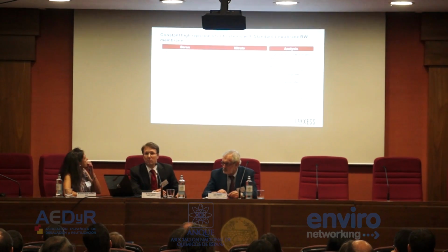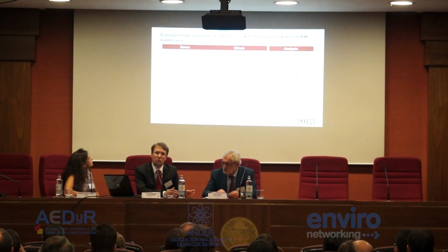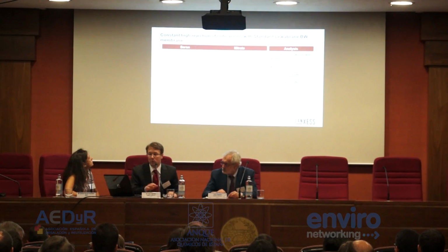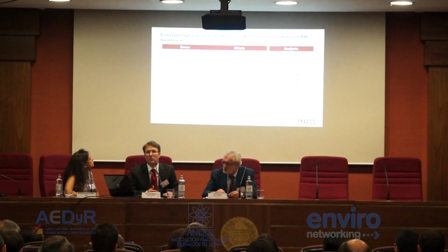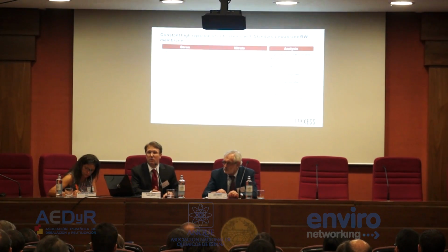So we made a test with boron at different pH. You know, boric acid is not charged at a pH below 9.2, then it becomes negative, and therefore you have an increase in rejection. That is the reason you increase the pH before the second pass in the seawater desalination plant. But we could show that we already have a higher rejection also in the lower pH region. This is simply due to the higher cross-linkage. We have a lower effect of electrostatic interaction, but due to the lower pore size we already have a higher rejection, also at low pH.